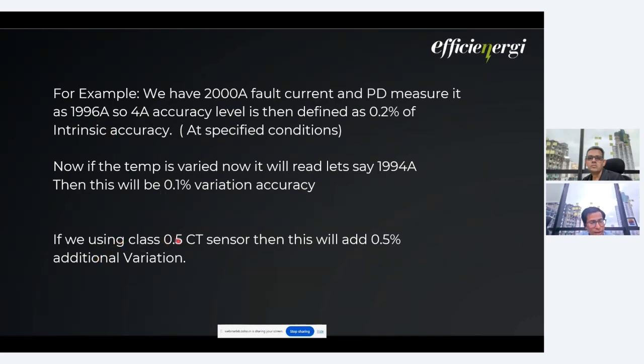Then, let's say we are using a 0.5 class CT sensor, which will add an additional 0.5 variation into the system. So the total accuracy of the system would be the intrinsic accuracy plus 1.15 times the square root of all the variations that are because of operating conditions. Additionally, the external factors such as the CT variation also have to be added. This gives the complete total time-current characteristics of that particular protection device. So it will not be a single line. It will always have plus and minus, that is, maximum and minimum specified.